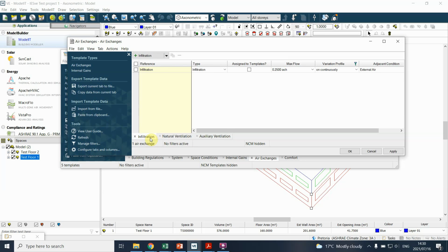Now, infiltration is something that's ever present. Infiltration refers to how leaky a building is, and in the South African conditions, it's quite varying. Some of the studies that have been undertaken have documented in the US leakage from 0.5 liters per second per square meter to up to 70 liters per square meter, or less than 2 air exchanges per hour to about 50 air exchanges per hour. So from very little to very high.